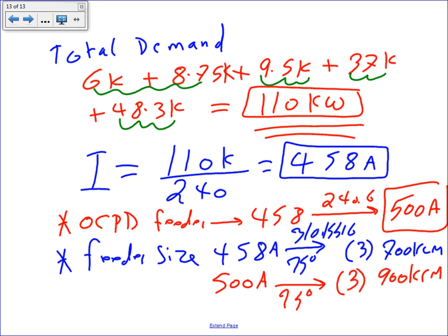Now, if you need my judgment, I would size based on the overcurrent protection device right here. That's what I choose. Why? Because if it's a panel, and this is a 500 amp panel, in the future you can add to this panel, right? So that's good futuristic thinking, envisioning what's going to happen in the future. I would size based on the overcurrent protection device. But though by code and fill, you can go as low as 700 kcmil, and that's okay. Do you want to parallel? Be my guest, parallel. I just don't want to get into paralleling because we've been running for a long time.